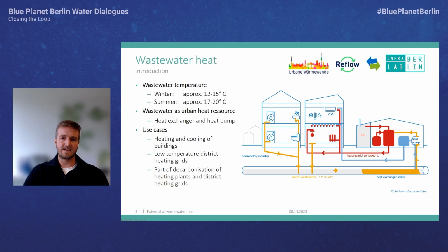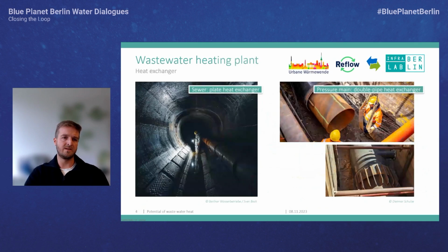How is this heat extracted? We basically have two technologies we use in Berlin, with already 25 projects in implementation or planning. In the sewer system, we see plate heat exchangers based at the bottom of the sewer, and the wastewater flows over this heat exchanger. In between these plates there is a fluid, water in our case, which extracts heat from the wastewater, then used by heat pumps.